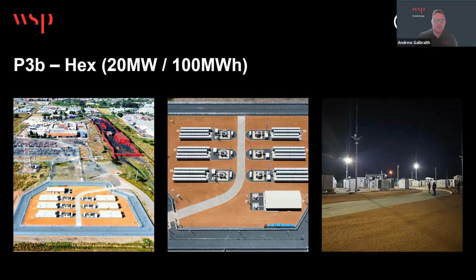So there was a mobile transformer station put in. It was an old Eskom mobile transformer unit that had to be refurbished and was utilized for the duration of the project. We also had to install oil dams as the transformers were upsized from 10 MVA to 20, which required new oil dams to be installed in the substation.